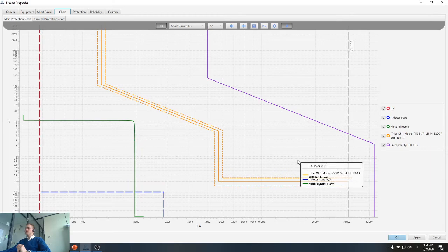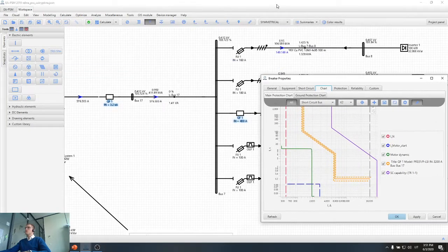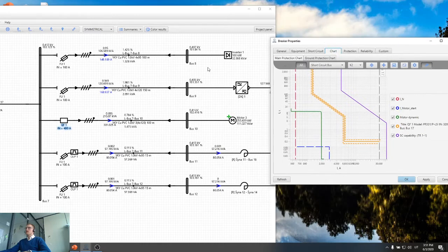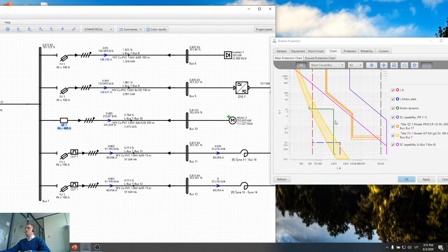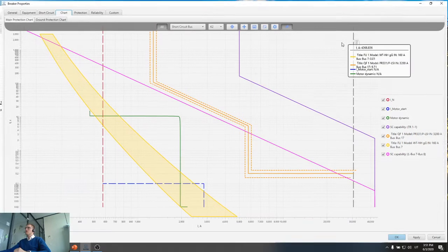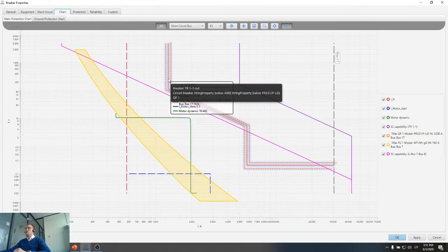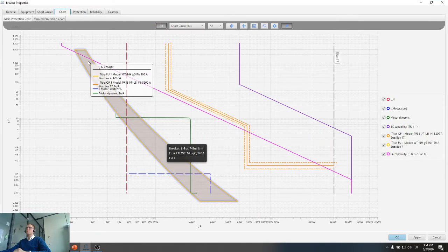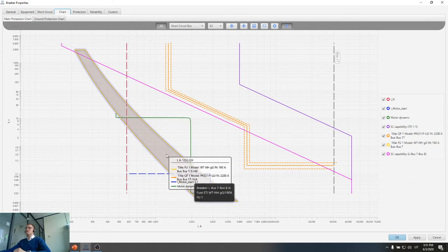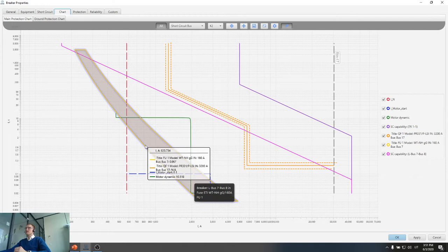So how to check selectivity within our software? You can do it in this way. When you have a single line diagram with other protections created, you can simply take any protection devices from the network and put them on the same protection selectivity chart with the incomer breaker. So now we have our incomer breaker, and we have our fuse. You can see that the fuse curve is quite far away to the left side, which means that our fuse is selective with our incomer breaker.